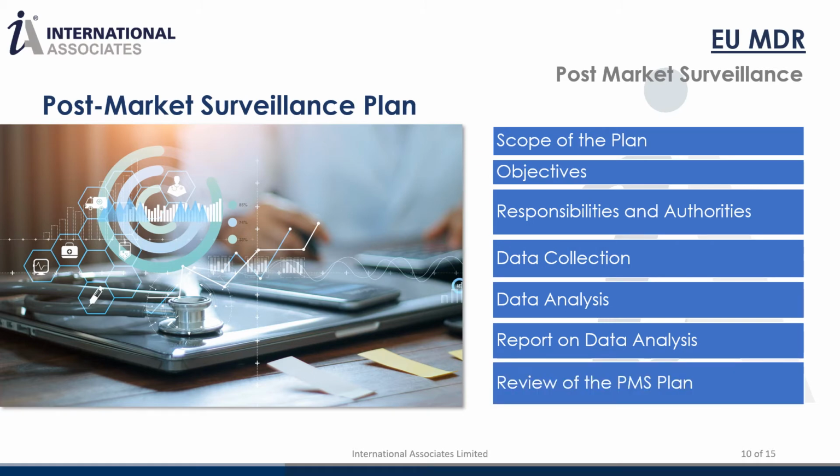The PMS plan must be prepared before placing the medical device on the market for the first time and updated as necessary during the product lifecycle. This means, if you have a new device for the first time certification, you need to prepare the PMS plan, which would then form part of your technical documentation. If you appoint an EU responsible person, it is likely they will want to review this as part of their due diligence.